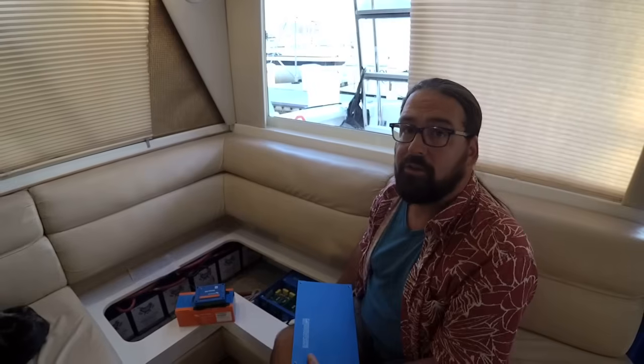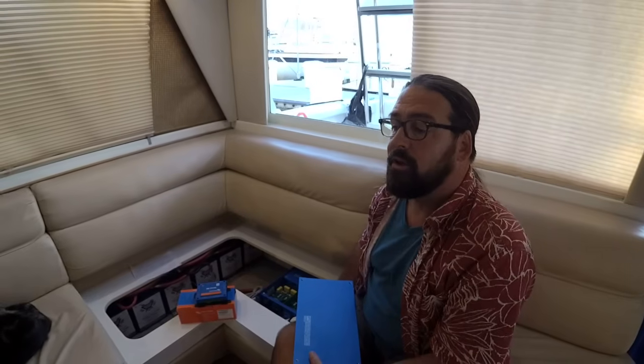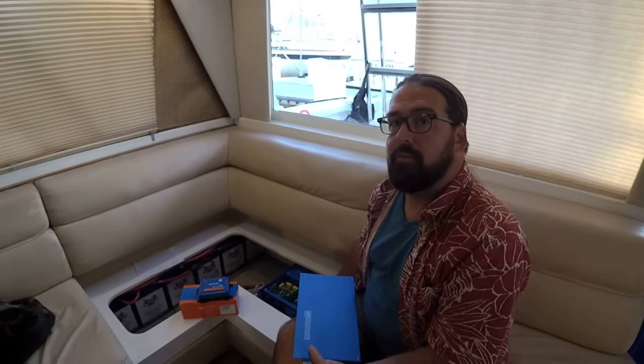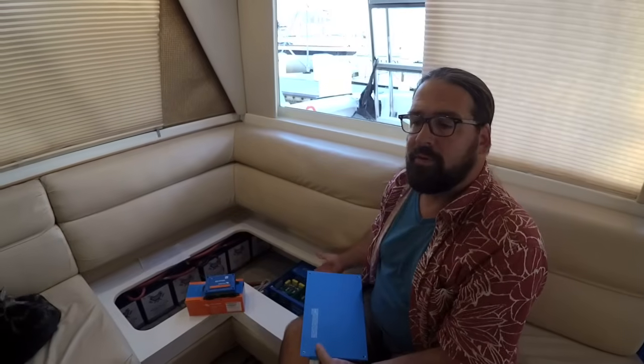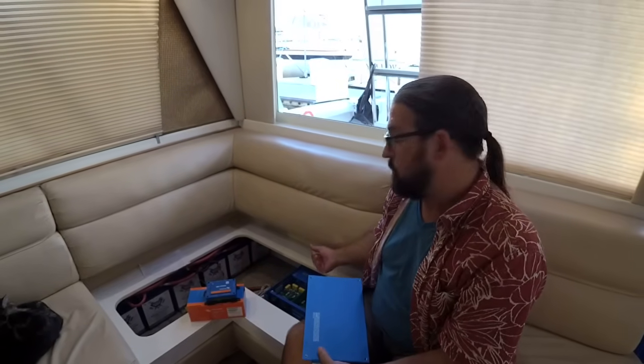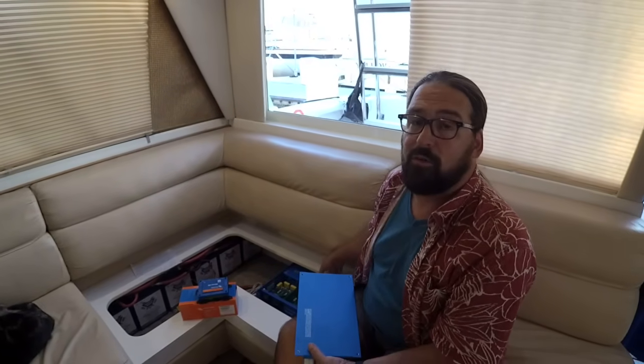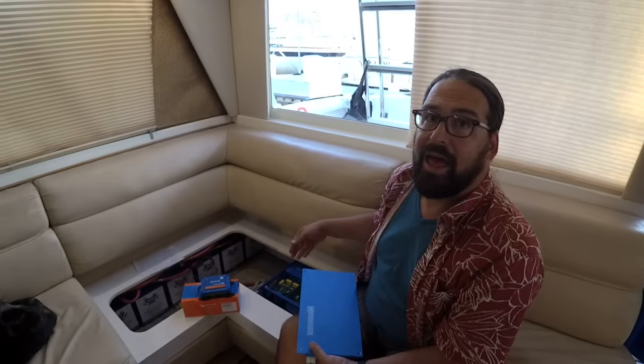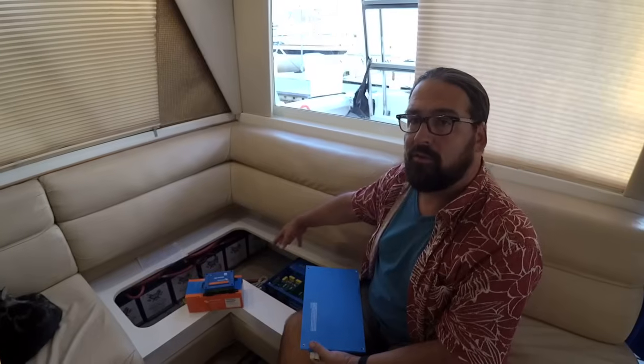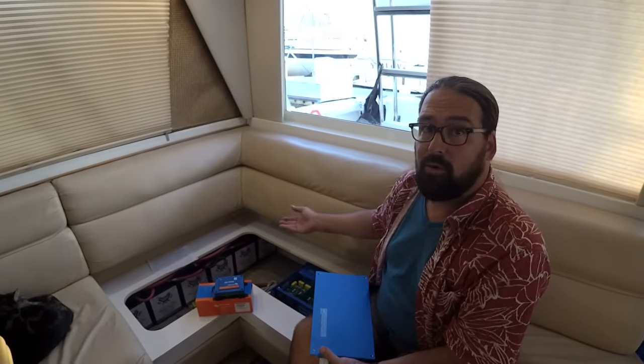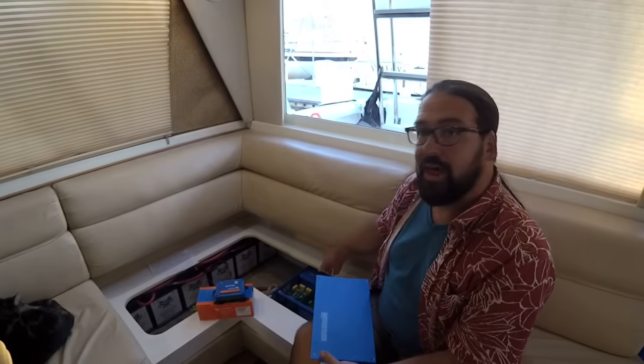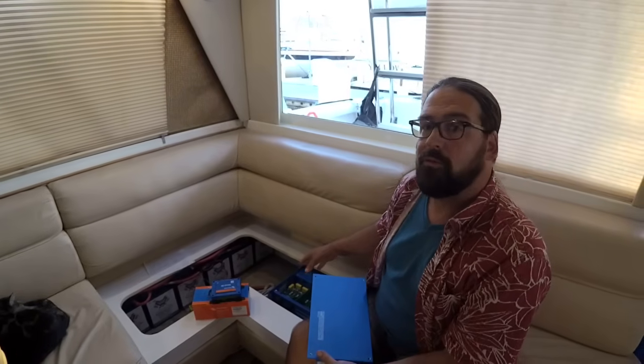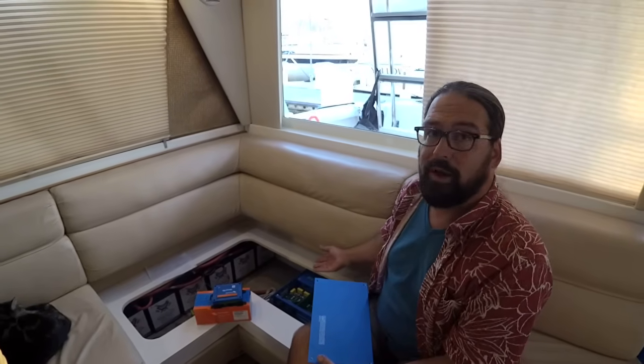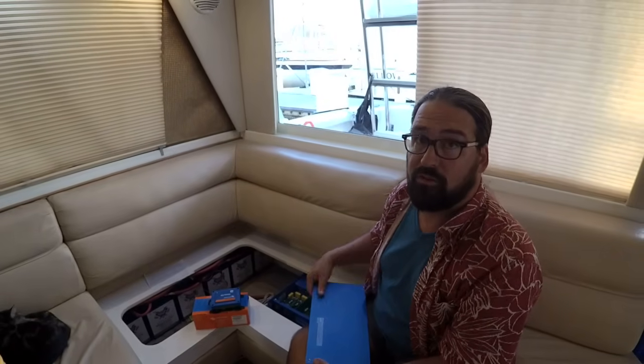What Quattro means is it's got 2 inputs and 2 outputs, so both the generator and shore power come into here, and it can use its boosting capability to boost up either one of those power sources. In our case we've got just a 6,000 watt generator, so if we have spikes of higher loads that would overload it, it just combines with battery power. Or if we're at a marina with only 30 amp service, or even 20 or 15, we just tell the inverter, and it will combine battery power with shore power, so we will never blow a circuit on shore.